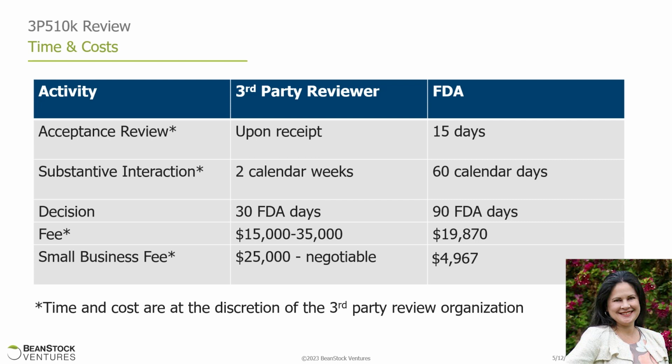FDA, you're looking at about $19,000 to $20,000. And the small business fee, we find a lot of customers will ask us if we can entertain the small business fee. We can within reason, so I would say that's negotiable, and I think each third party has their own policy around that. But if you're really looking at cost and you're not too concerned with your time to market, then FDA might be a better option for you, because this is under $5,000 for small business. You do have to show that you are a small business. There's some documentation that's required. I don't know the specifics, but it is something that you need to consider and qualify for.